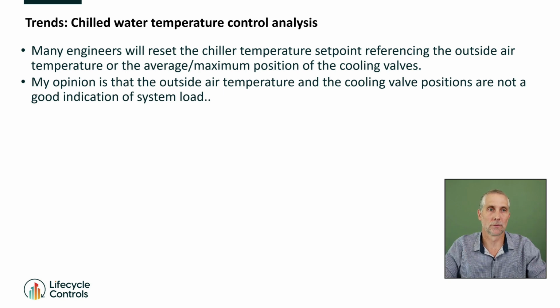I'm just picking this one part out. Many engineers will reset the chill water temperature set point referencing the outside air temperature or the average or maximum position of the cooling valves. My opinion is that the outside air temperature and the cooling valve positions are not a good indication of system load. So this discussion is, I think why I got this here, that I'm going to give you an example of where we optimize something, we develop a smarter control strategy, and we download it. It doesn't work at all.